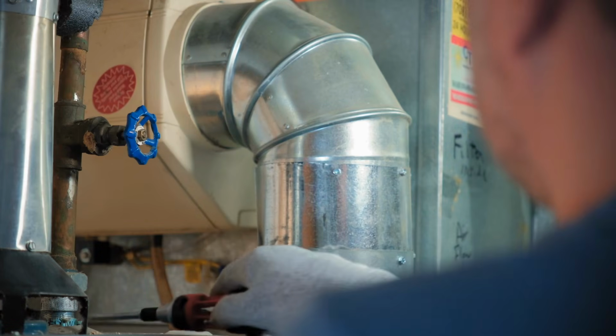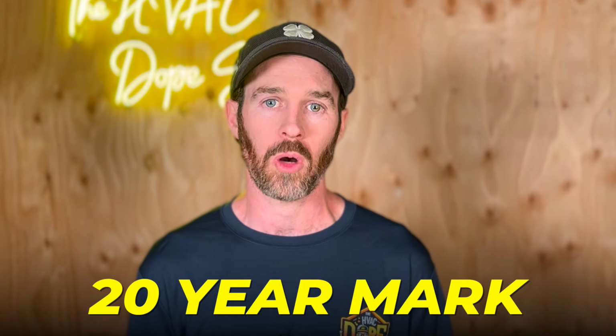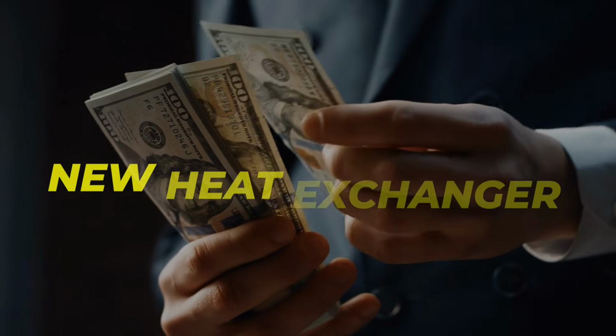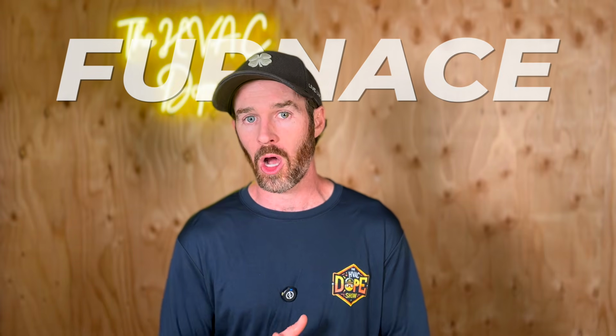Basically, you can repair the system, but oftentimes we advise against repairing a system because your heat exchanger typically won't start to crack until the 15 or 20 year mark. Cracks tend to develop on older systems. It's normal wear and tear. Once something cracks, it's typically a sign that the system is basically ripe for replacement. At that age, rather than spending the money on a new heat exchanger, that money would be better spent on replacing the system with a more efficient, newer furnace or heat pump combination system. But the bottom line is that repair is an option.